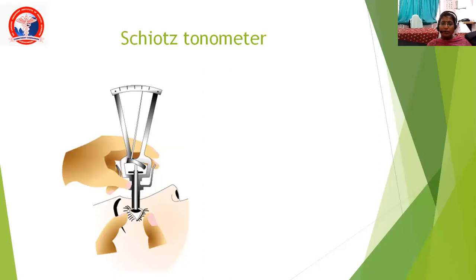Next is Schiotz's tonometer, which is an older type of contact tonometer. It is kept on the cornea and the reading is taken from the scale in the Schiotz's tonometer. The corresponding readings are then taken from the table provided with the instrument.